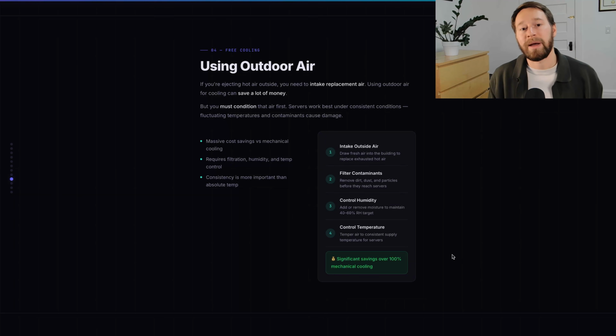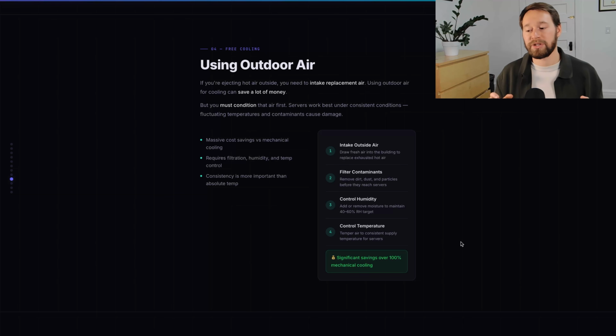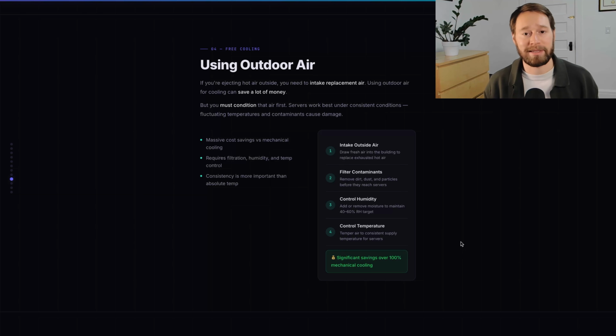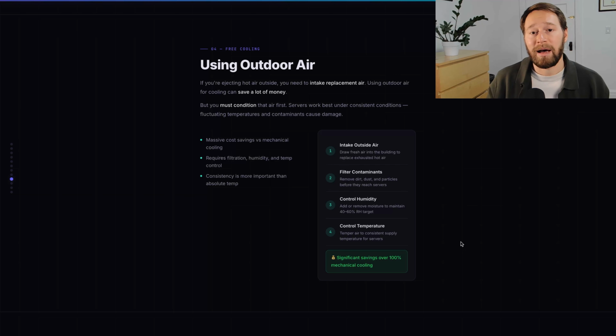Free cooling is another way that, if you're building your own facility, can reduce a ton of cost. Air conditioning uses 30 to 40% of the power in your data center, just as a typical estimate. So if you have 100 kilowatts of computer systems running, you'll probably want 30 to 40 kilowatts of air conditioning to cool it down. You can get away with using outdoor air, sucking it in from outside, running that colder air through your systems, and ejecting the hot air out of the building. But there's a lot you have to do to ensure it's suitable, which comes back to the temperature and humidity of that air, and you'll want a lot of filtering on it.